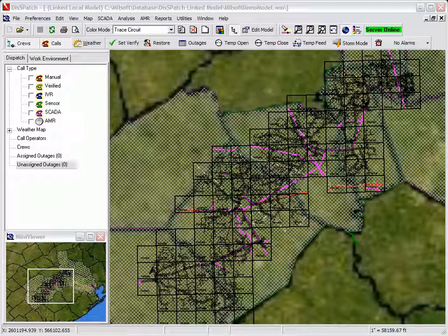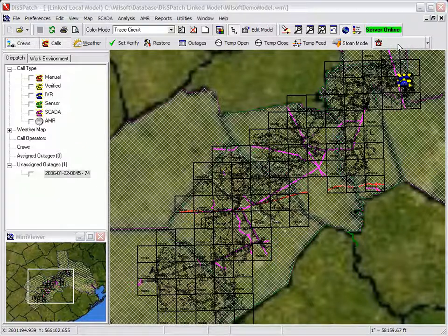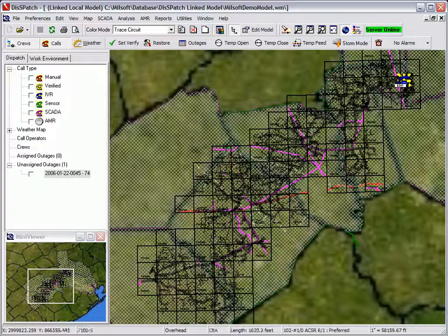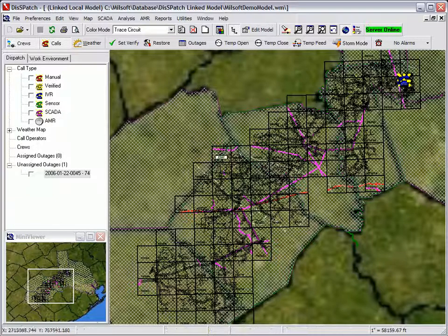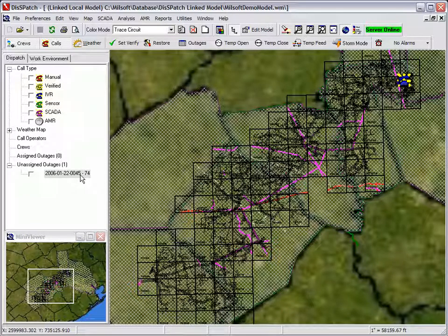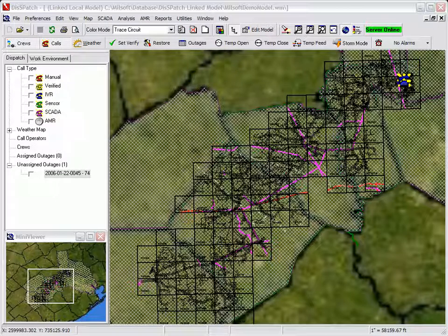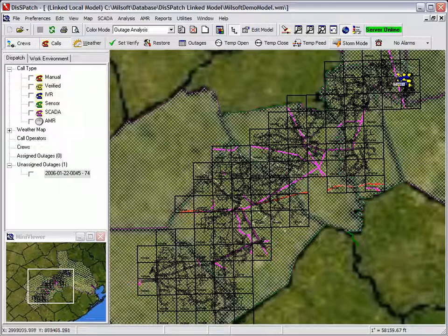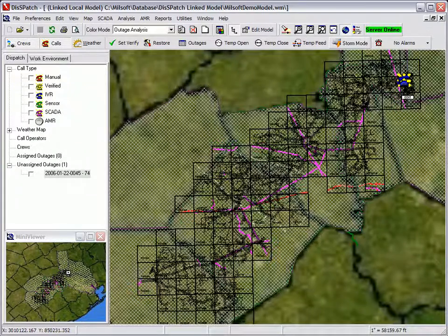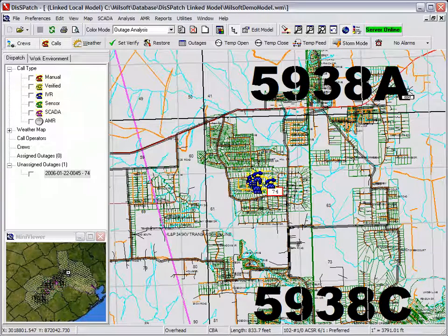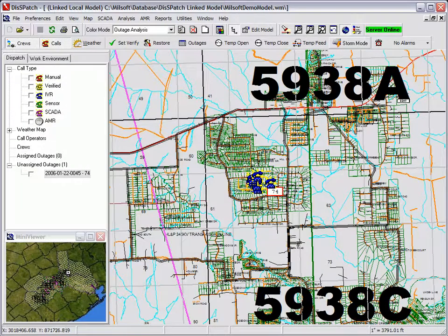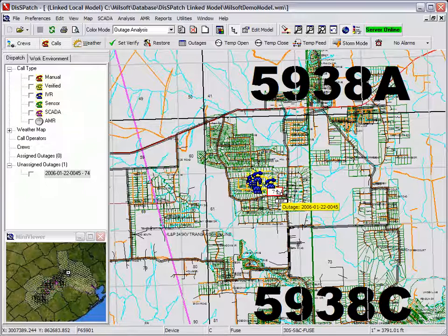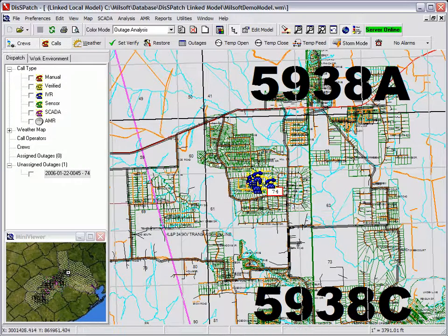The dispatcher notices and hears an alarm that a new outage has appeared. The dispatcher acknowledges the alarm. The outage tree view on the left shows an unassigned outage on a fuse with 74 customers reported out. The dispatcher zooms into the suspected outage on the map and turns off the street and map layers for a clearer picture of the outage in progress.